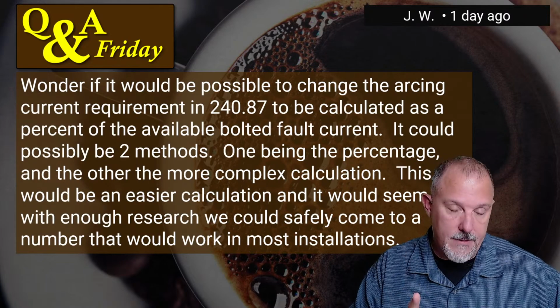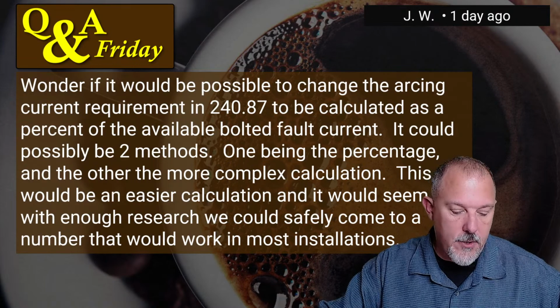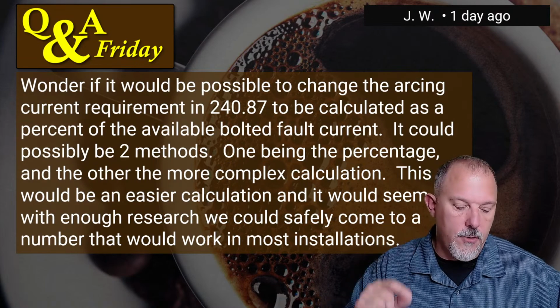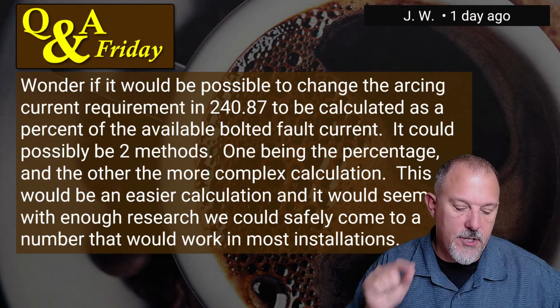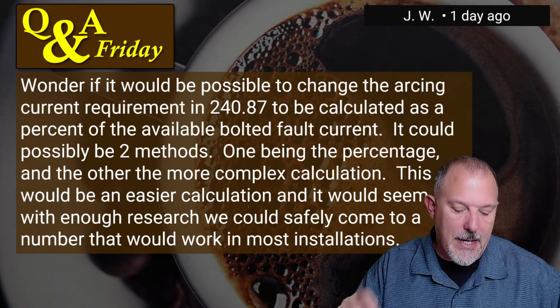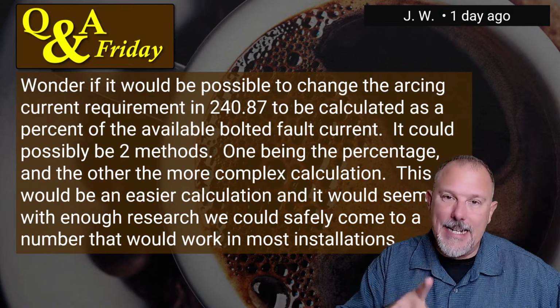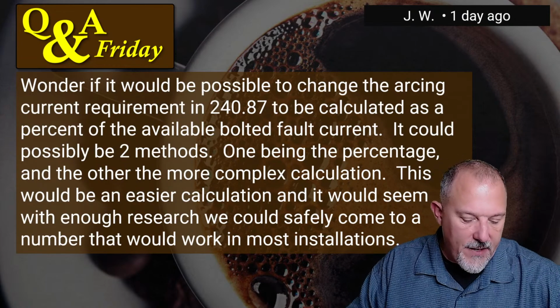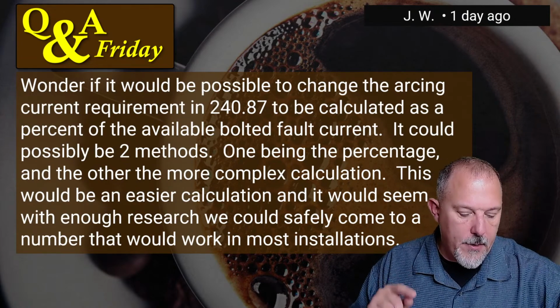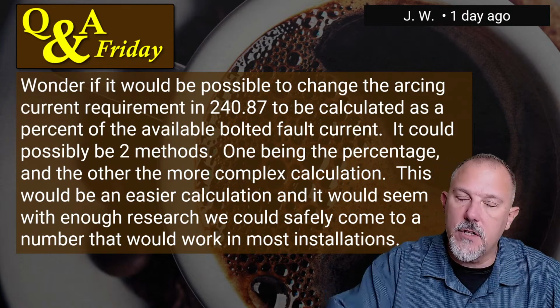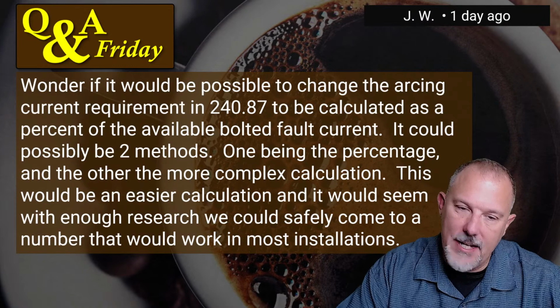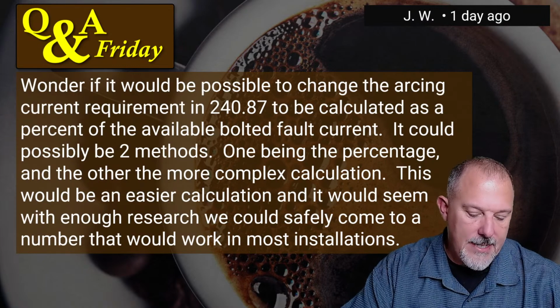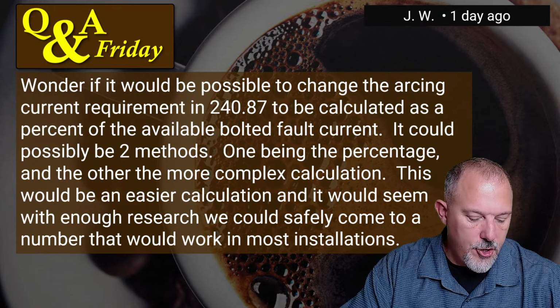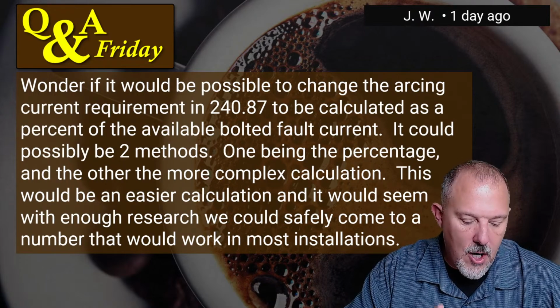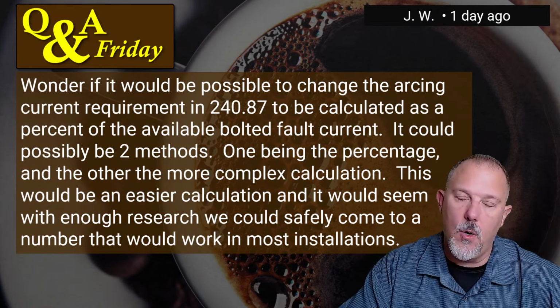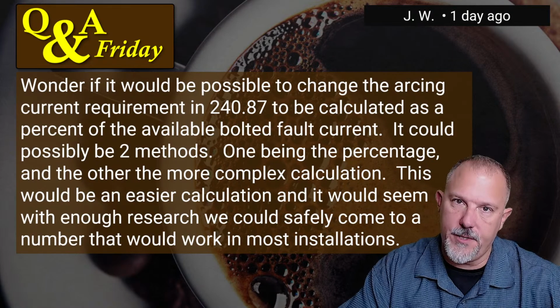240.87 says, where the highest continuous current trip setting for which the actual overcurrent device installed in a circuit breaker is rated or can be adjusted is 1200 amps or higher, A and B apply. And in A, it says documentation shall be available to those authorized to design, install, operate, or inspect the installation as to the location of the circuit breakers. And it says documentation shall also be provided to demonstrate that the method chosen to reduce clearing time is set to operate at a value below the available arcing current.